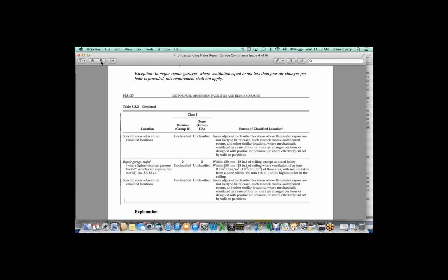Typically, the one question we always get asked by a lot of people is whether or not you have to make the entire area that's 18 inches or below from the ceiling compliant with the NFPA 30A, which basically would make your electrical classification, which is again looking at the same chart. We looked at that compliance as far as what it would take to relocate all the electrical versus what it would take to make that area unclassified by adding in exhaust fans, which you can see clearly in the chart is okay as long as you move that much air in a certain amount of time.